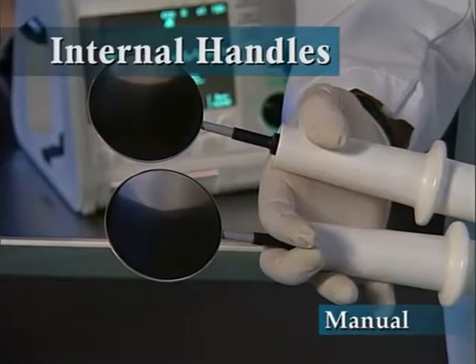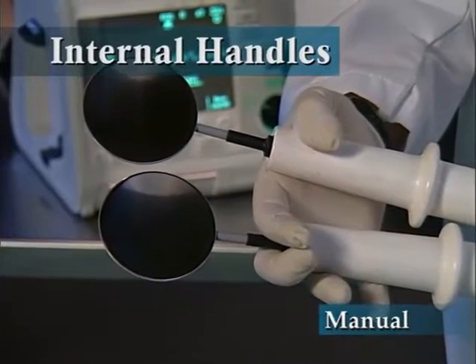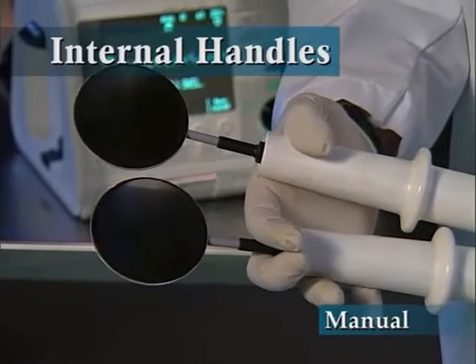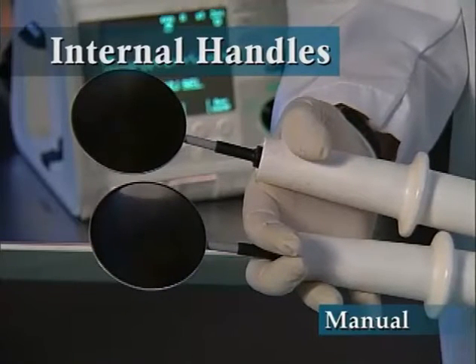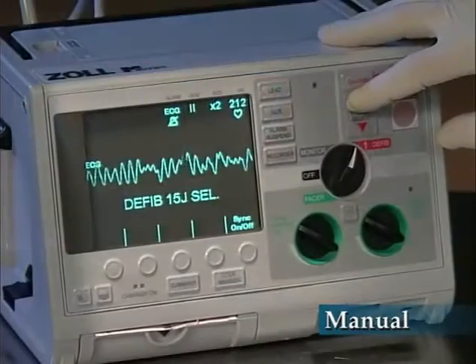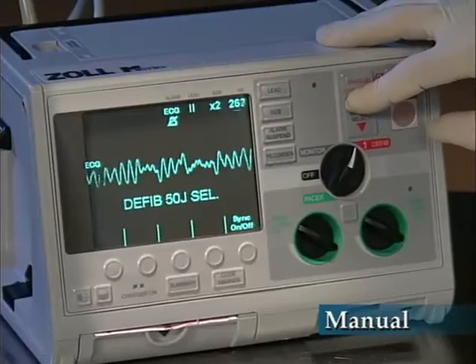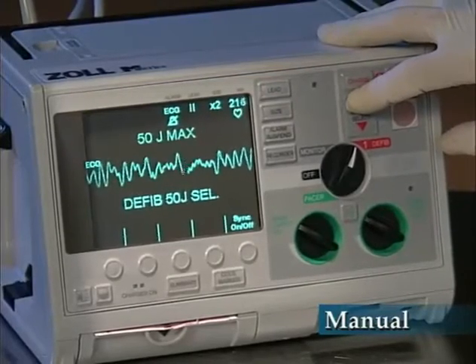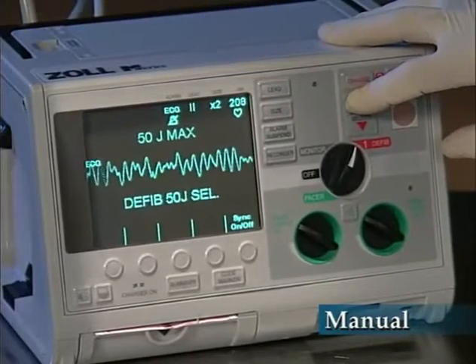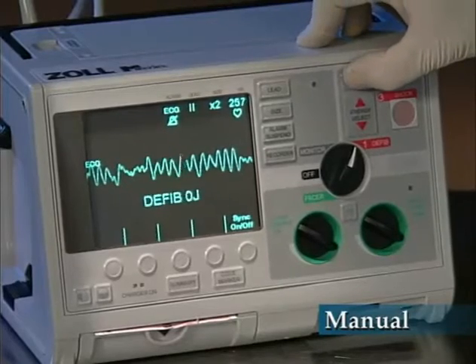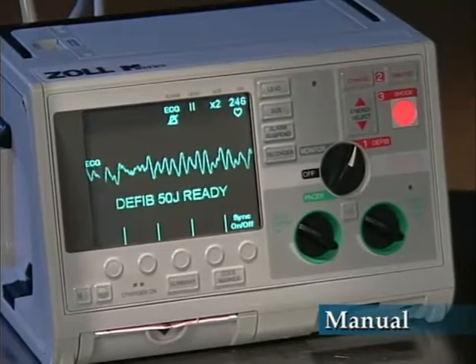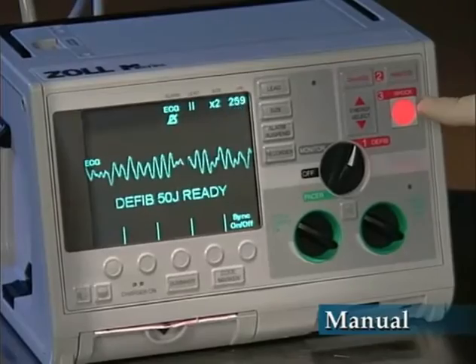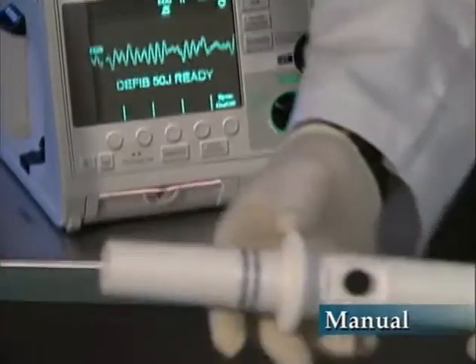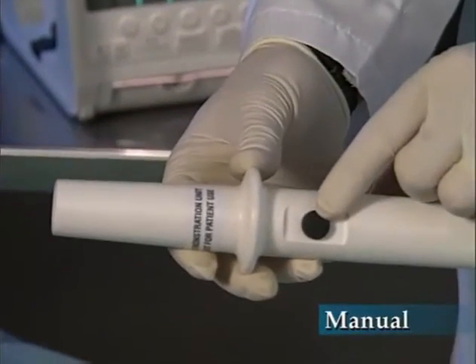Internal defibrillation is available using ZOLL autoclavable handles and electrodes. Autoclavable internal handles are only for use in the manual mode. They do not operate in the advisory or semi-automatic modes. When using internal handles, the defibrillator automatically limits its energy output to a maximum of 50 joules. The defibrillator is charged by pressing the charge button on the front panel and discharged by pressing either the shock button on the front panel or the discharge button incorporated in the internal handle sets.